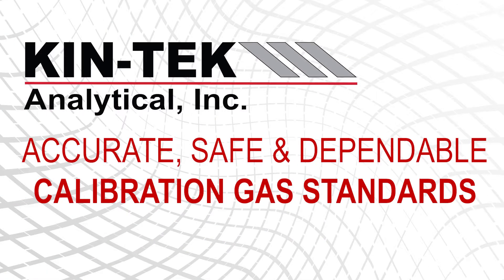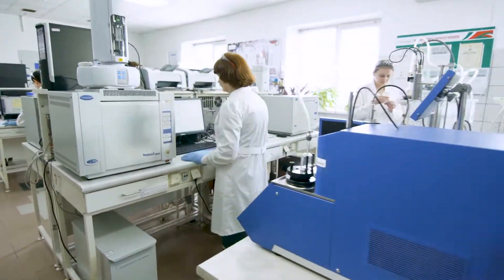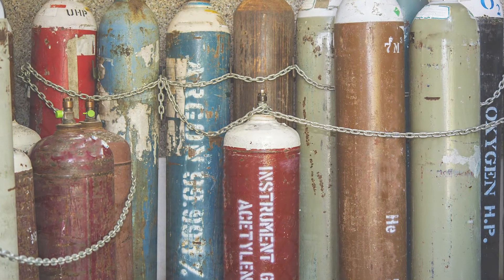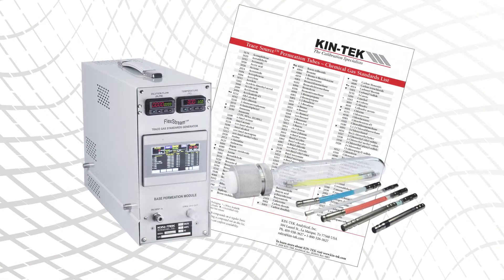If accuracy and safety during gas calibration is important to you, then Kin-Tek Analytical has a solution. Labs around the world calibrate analytical equipment with a variety of Kin-Tek gas standard generators incorporating trace source permeation tube technology. Kin-Tek calibration systems can replace gas cylinders using trace source permeation tubes with over 550 different chemical standards that are NIST traceable.